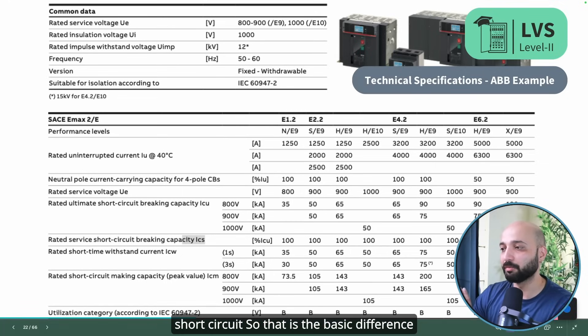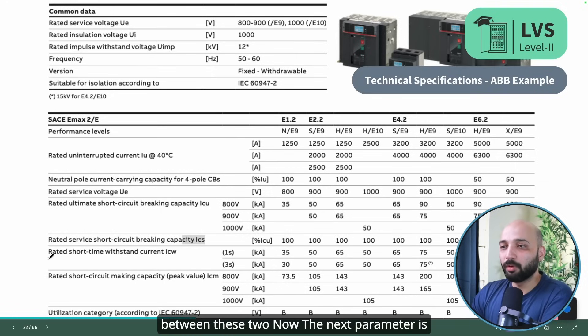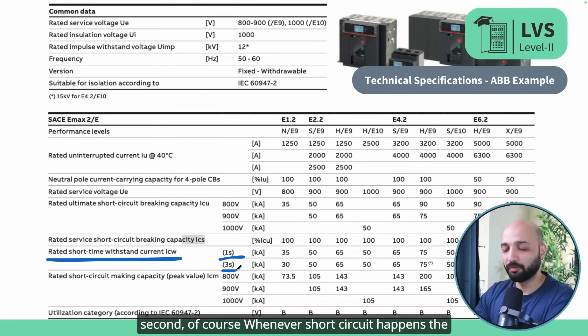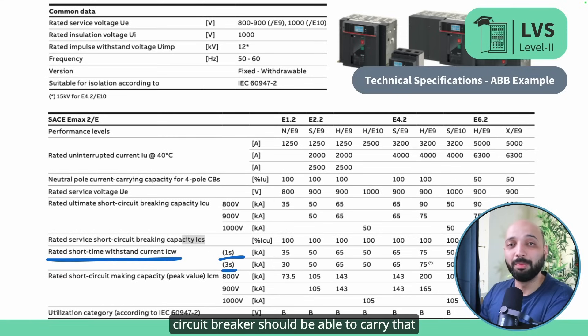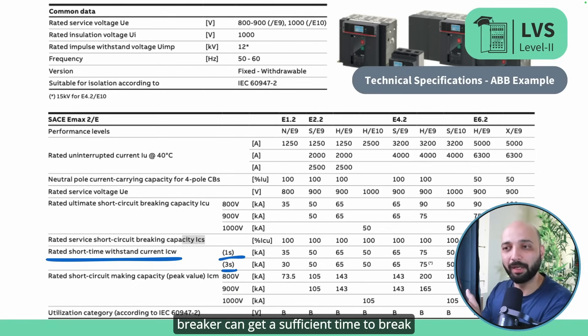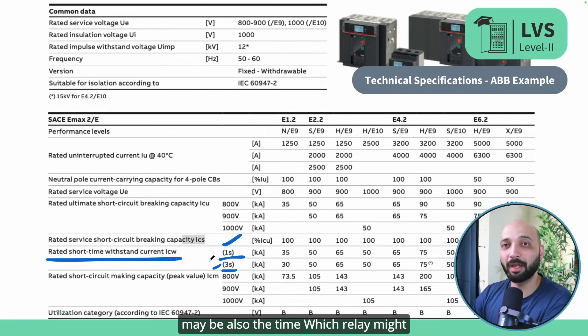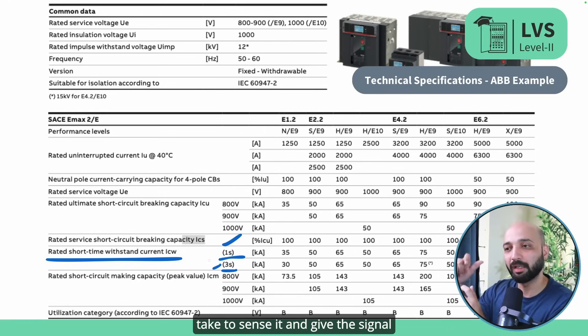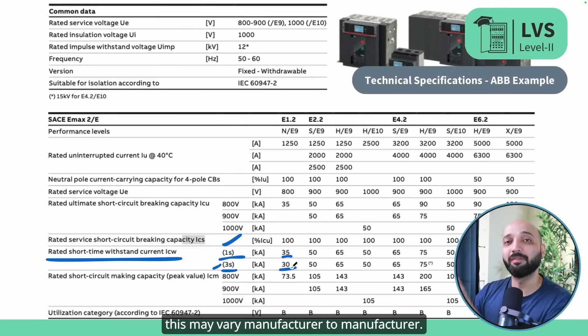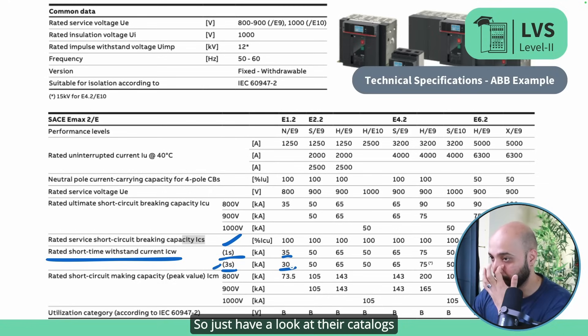The next parameter is the rated short circuit withstand current, given for one second or three seconds. Whenever a short circuit happens, the circuit breaker must be able to carry that current for a certain time so it has sufficient time to break, and also to allow the relay time to sense and send the trip signal. For one second, the withstand rating is 35 kA, but if it continues for three seconds, the rating drops to 30 kA. This may vary by manufacturer.